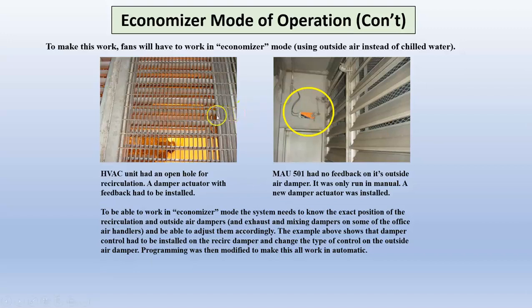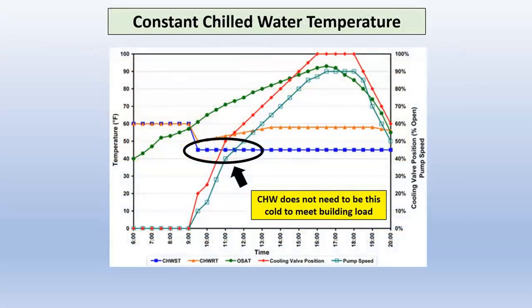So in this case, like the reset, the return air, there was no damper there on this big air handler. So I had to put one in so we could control it. Otherwise, if it's wide open, I'd never get the right ratio of outside air to return air. So those are the things you need to look at if you're doing a retrofit.